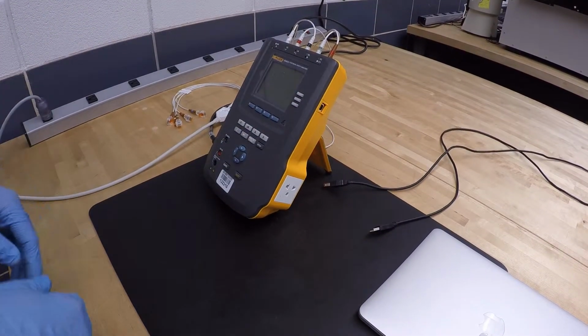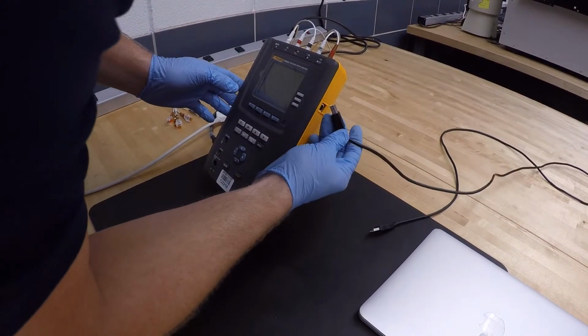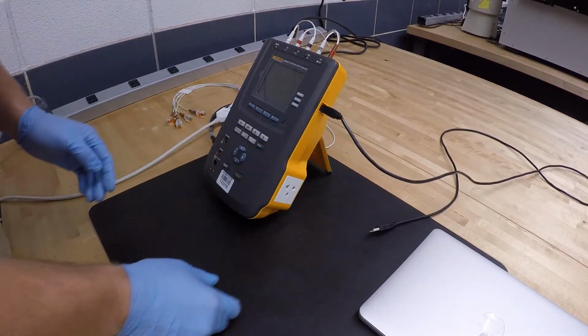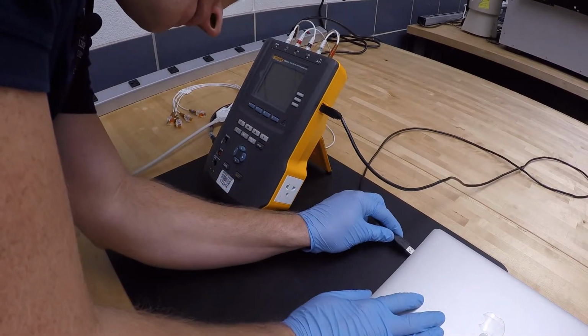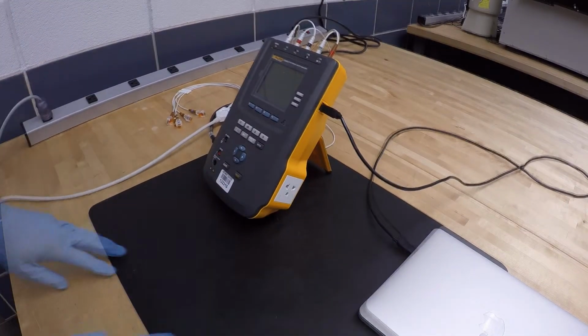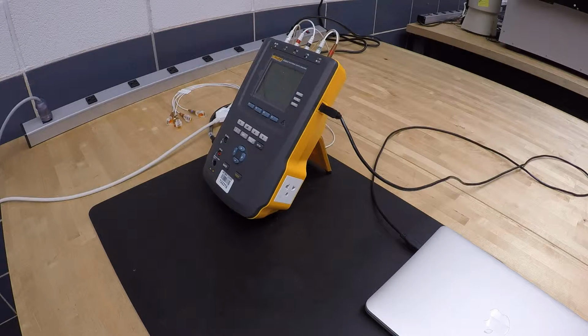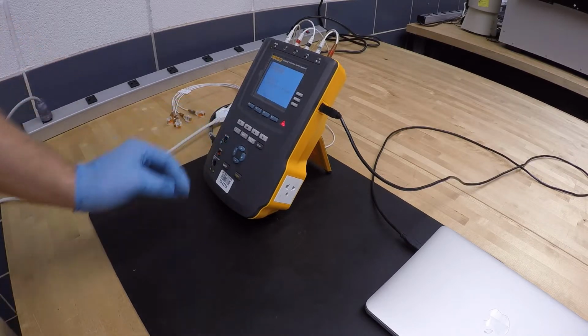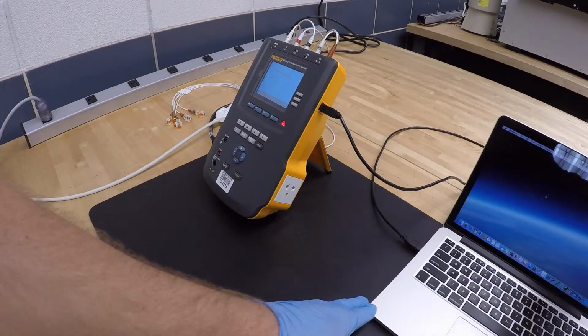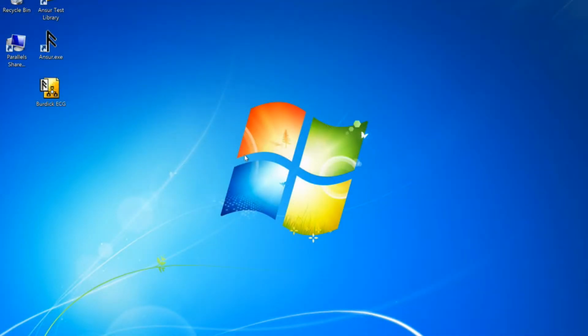With the ECG leads plugged in, we will now plug in a USB cable into the side of the analyzer and then plug it into the computer. Now that we have all the proper cables connected to the devices, we can now power on our analyzer and computer. Now that we have all our cables plugged in and devices turned on, we can run our software. We're going to be using a template that we created with the Ansur program. We use this to check the leakage current of the device. So we're going to launch the template right now.